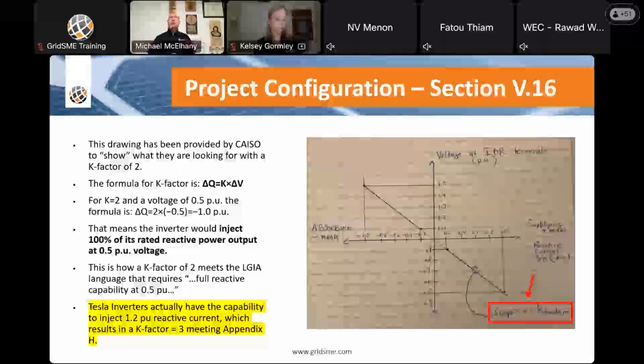And I just, again, want to quickly say there is no requirement for a K factor of 2. A lot of times you'll hear the statement that CAISO requires a K factor of 2. That is not correct. You have to have full reactive capability injected at 0.5 per unit voltage, which means if you have 1.0 per unit current injection, it will be a slope of 2 in order to achieve that. But there is nowhere in Appendix H in your LGIA that it says you have to have a K factor of 2. So this is kind of the background for that.